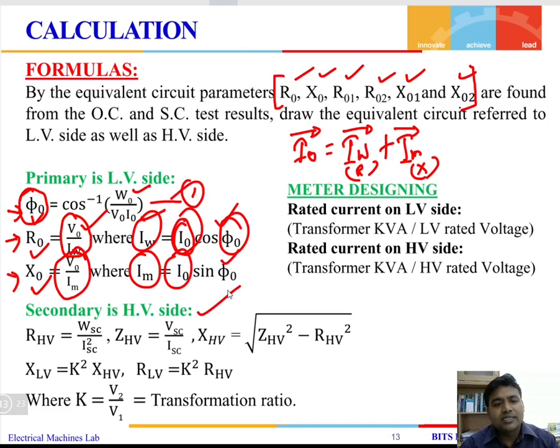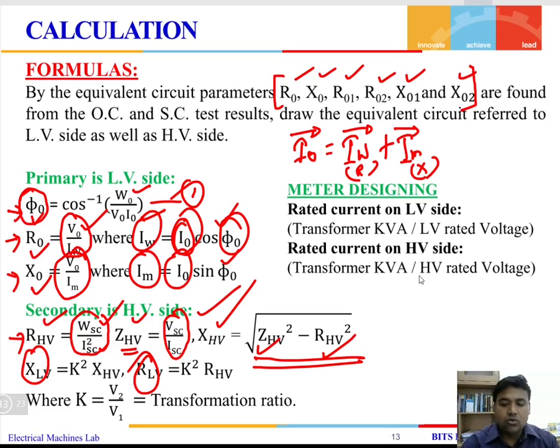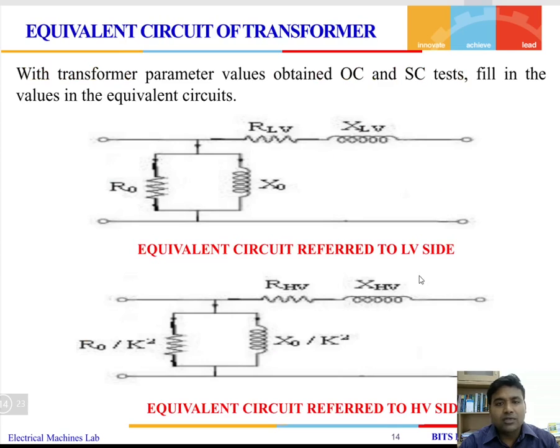Using the short circuit test data, first obtain the resistance on the high voltage side: R01 = Psc / Isc². The impedance Z01 = Vsc / Isc. Once we have R and Z, the reactance X01 = √(Z01² − R01²). We can then transfer the data from the high voltage side to the low voltage side or vice versa depending on our requirement.